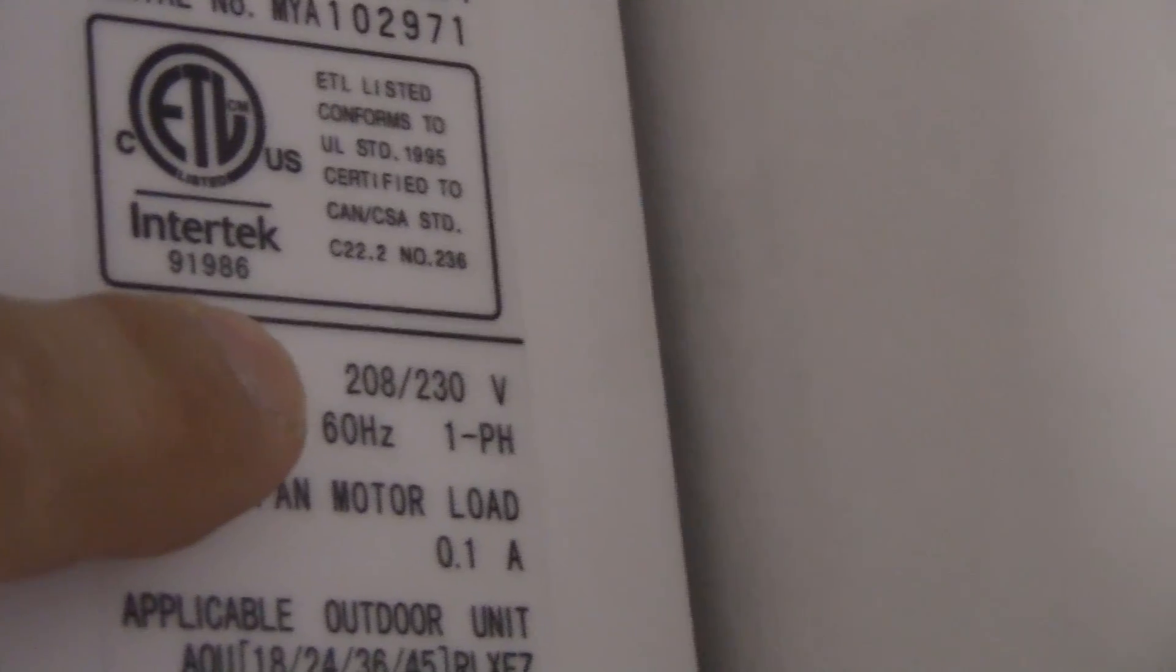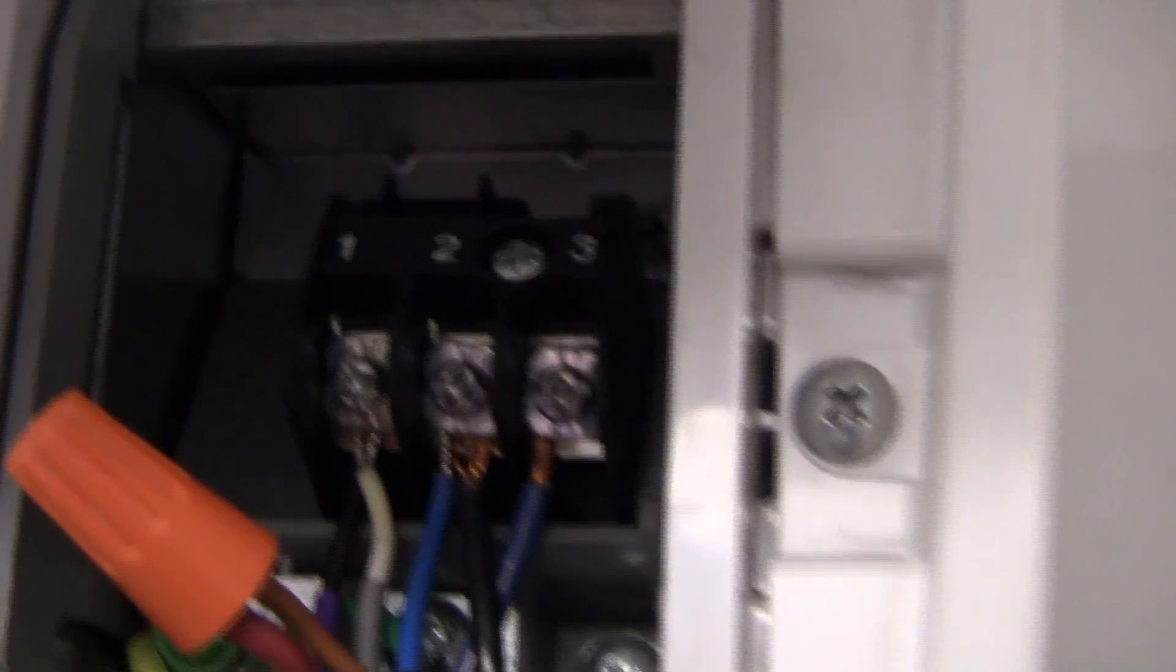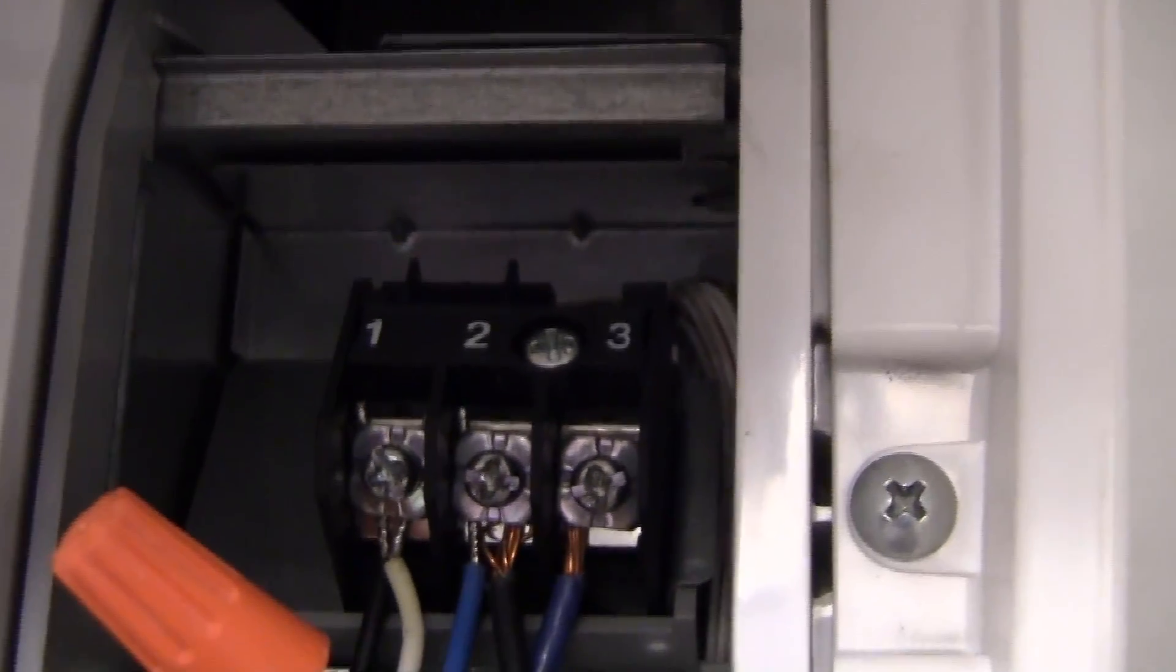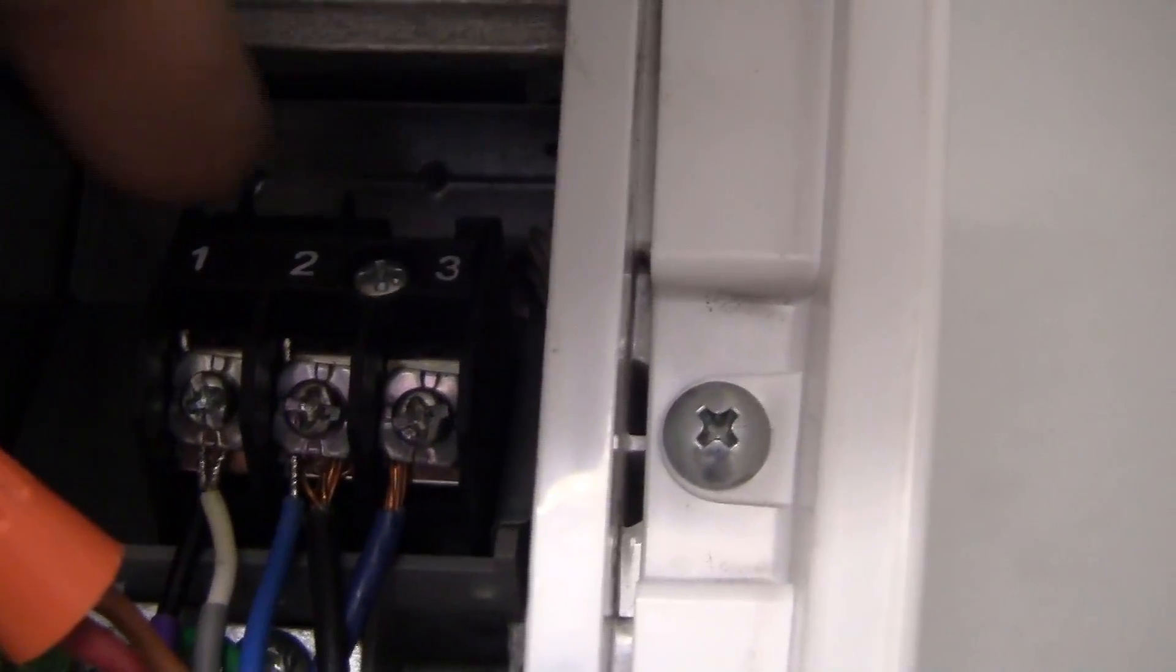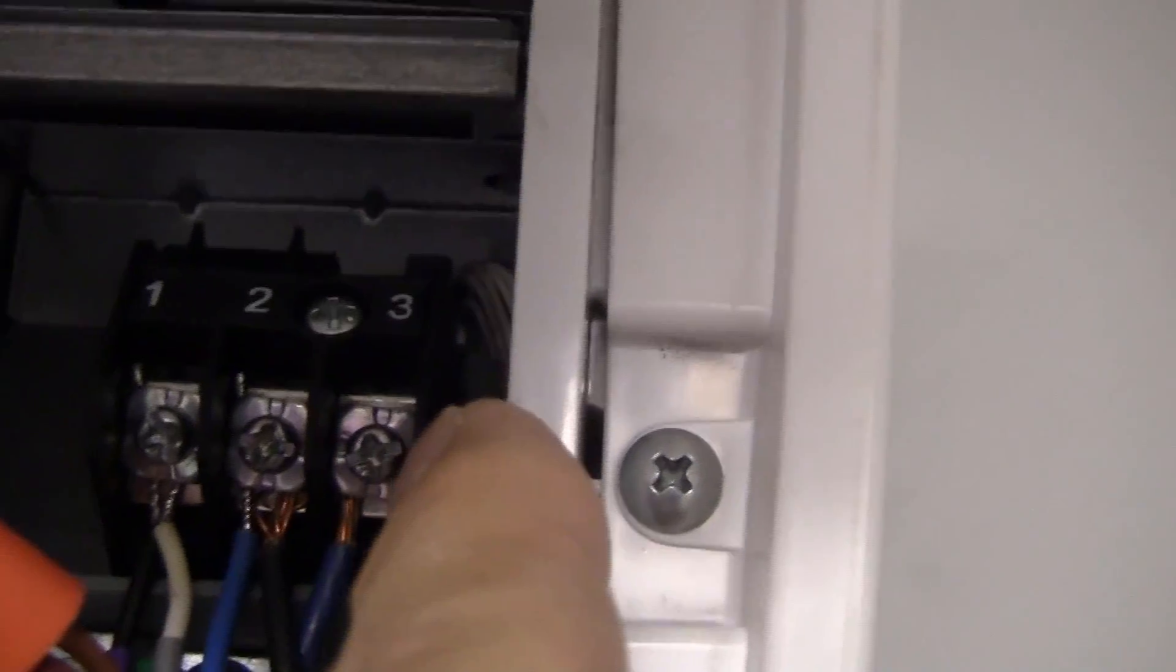So the evaporator that we're dealing with right here is a Fujitsu and you can see on the data nameplate that the voltage is 208-230 volts single phase and it's pulling not even one amp. I currently have the breaker off. When you're looking at your lines you have one, two and three. This is L1, L2 so that would be your hot 230 volts across those terminals and then on line three that's the communication wire that varies in voltage from 40 to 100 volts.